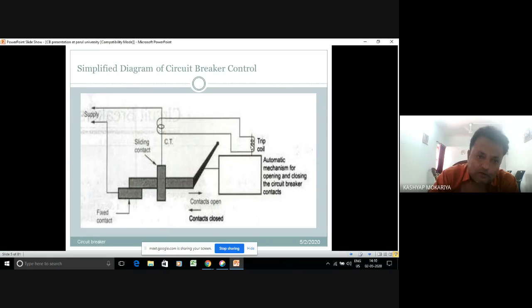Now say I have taken an example of an induction motor. Assume the induction motor overload setting has a different setting, and the induction motor short circuit setting is a different setting. Suppose the instantaneous setting for the motor should trip within 3 cycles. For that, suppose my motor rated current is 132 ampere. So 132 ampere into 6 is my starting current, divided by 0.75 to consider the lower voltage, to account for the amount of the starting current, because the breaker should not trip on that starting current. So it has a different requirement.